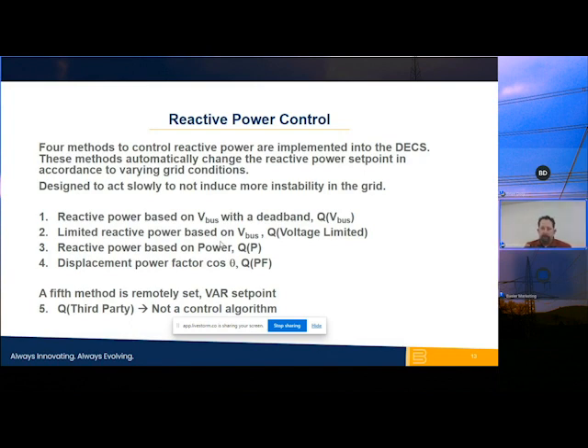In order to maintain grid stability, we've implemented 4 methods of reactive power control into the DECS products. These can automatically change the reactive power set point within the DECS according to the varying grid conditions. It's designed to act more slowly, and we're not trying to induce more instability of the grid. We're trying to make the grid more stable with these particular controls. So this is an outer loop type control. It's more of a slow bias signal into the main control algorithm of the DECS themselves. So it's an algorithm on top of the main control algorithm. We have developed 4 methods of doing this within the DECS products.